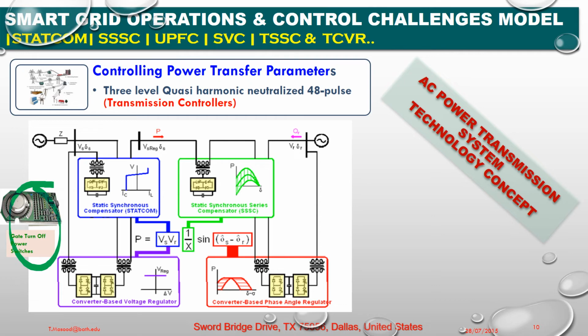Okay. Now, after application of GTO, IGBT, MOS, IGCT, MTOs depending on the power rating. So same here, this is my P equals V, sending end voltage, receiving end voltage, and my sending end and receiving end angle, and this is my line reactance. Okay. Now I am adjusting VS and VR by implementing a STATCOM. Okay, if you can see the STATCOM, it's showing the inductive mode of operation, and then it is also showing the capacitive and inductive mode of operation.